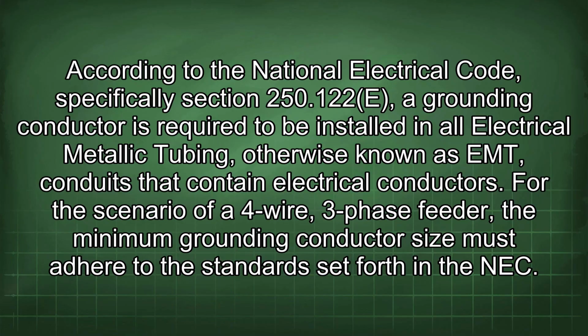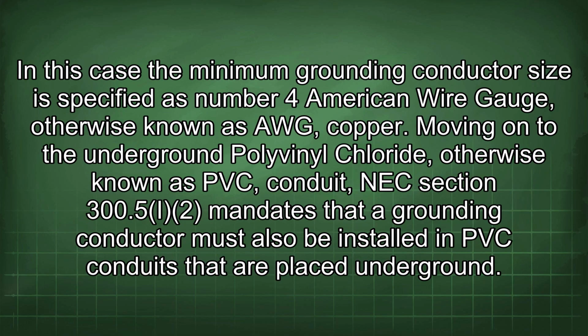According to the National Electrical Code, specifically Section 250.122(e), a grounding conductor is required to be installed in all electrical metallic tubing, otherwise known as EMT, conduits that contain electrical conductors. For this scenario of a 4-wire, 3-phase feeder, the minimum grounding conductor size must adhere to the standards set forth in the NEC.